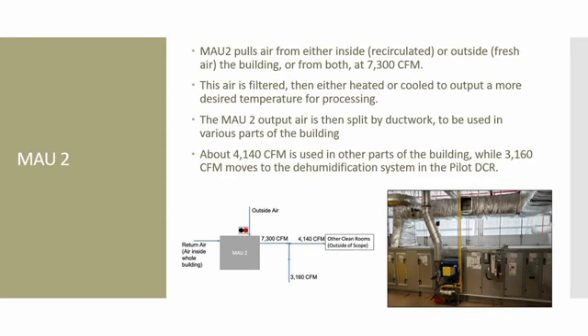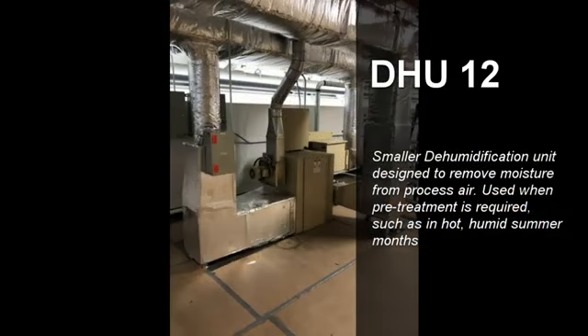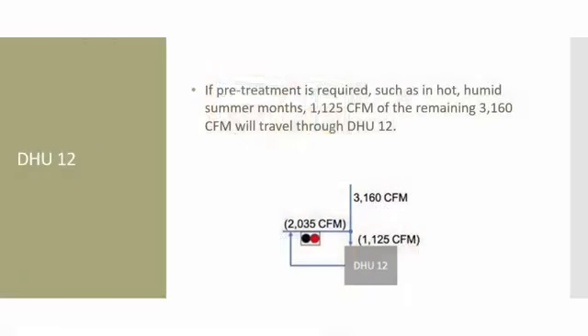The MAU2 output air is then split by ductwork. About 4,140 CFM of the air is used in other parts of the building, while 3,160 CFM moves on to the dehumidification units. The air then moves through DHU12, which is the smaller dehumidification unit designed to remove moisture from the process air. DHU12 is only used if pretreatment is required, such as in hot, humid summer months. If DHU12 is used, then 1,125 CFM of the remaining 3,160 CFM will travel through DHU12.